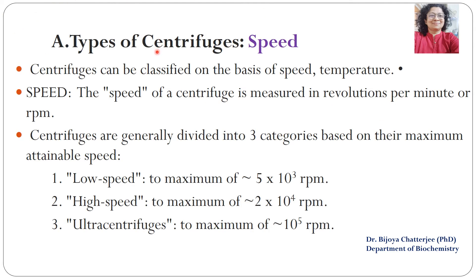Classification of centrifuges is based on different factors. The first classification is based on speed, measured in revolutions per minute (RPM). Centrifuges are divided into three categories: a low speed centrifuge with maximum speed around 5,000 RPM; a high speed centrifuge with maximum speed of 20,000 RPM; and an ultracentrifuge with speed around 1,00,000 RPM (10 raised to the power 5).